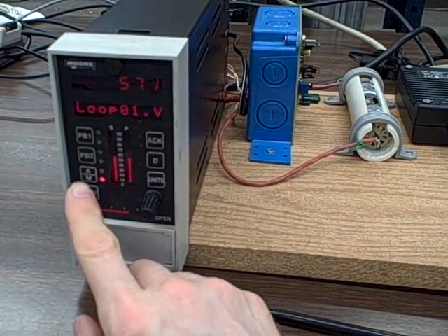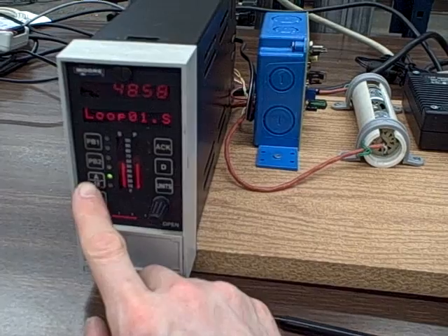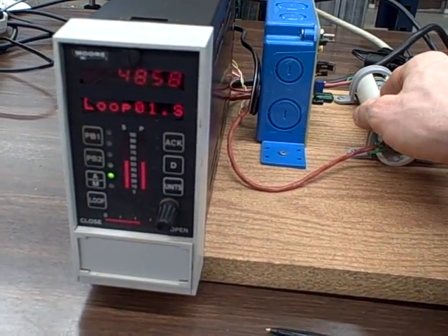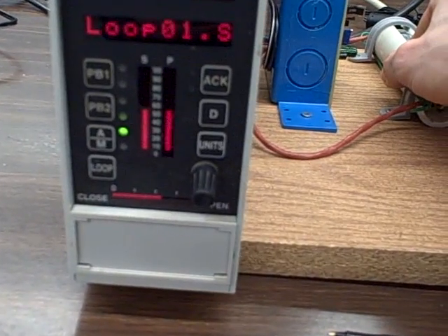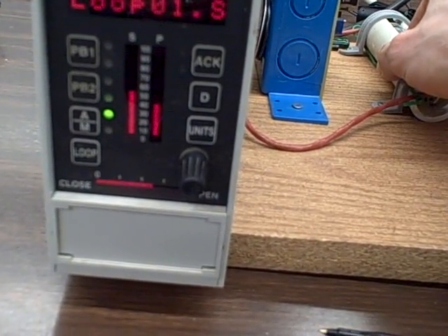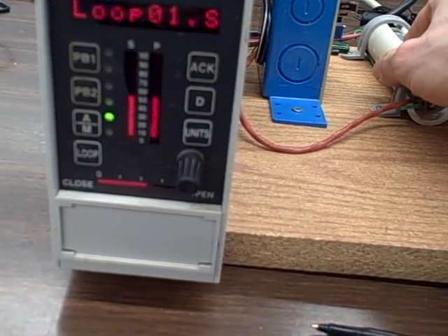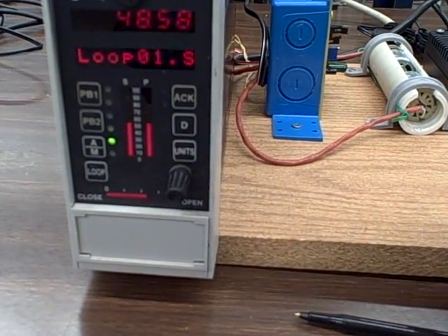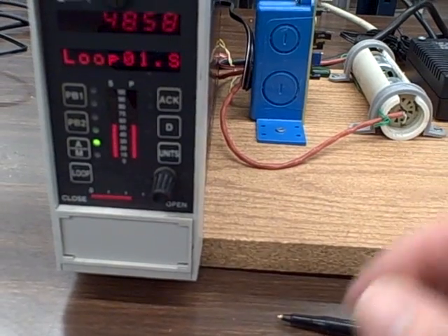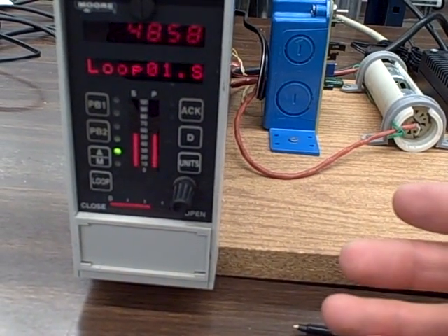When the motor is running at a certain speed, and I throw this into automatic mode, whenever it sees a change in the motor speed, such as when I touch my finger to the shaft of the motor to reduce speed, as speed goes down, it raises the output to try to correct for that change. As the speed goes down, the controller puts more electric power to the motor to offset or to counteract that load. That's called negative feedback.